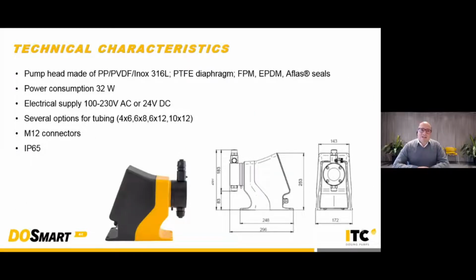What are the main technical characteristics for this pump? The pump head can be made of polypropylene, PVDF, or stainless steel. The diaphragm is always made of Teflon. It's a multi-layer diaphragm. And the sealing can be Viton, EPDM, or AFLAS. Given the characteristics of the motor we are using for this pump, the consumption is extremely low. Power consumption for DOSmart pump is only 32 watts.